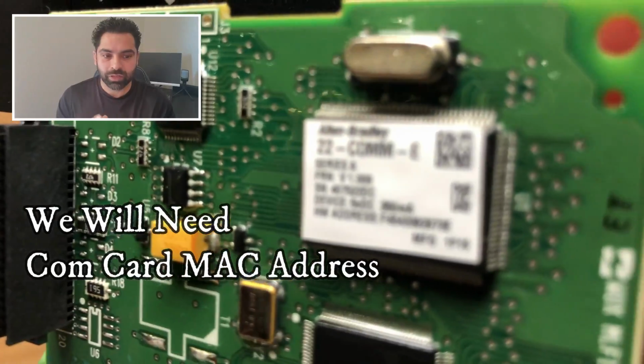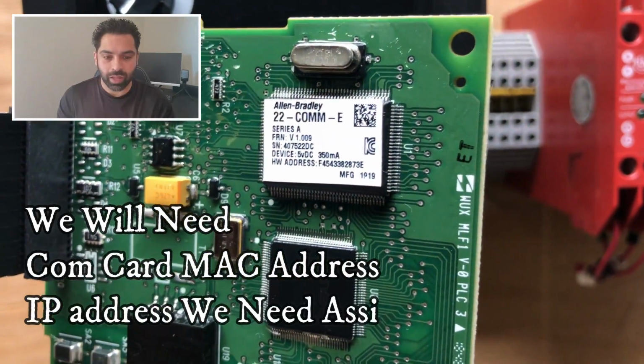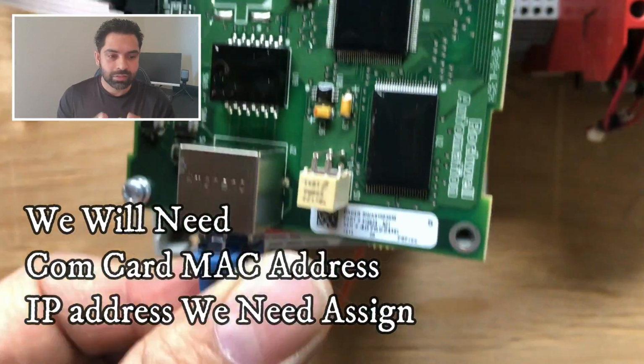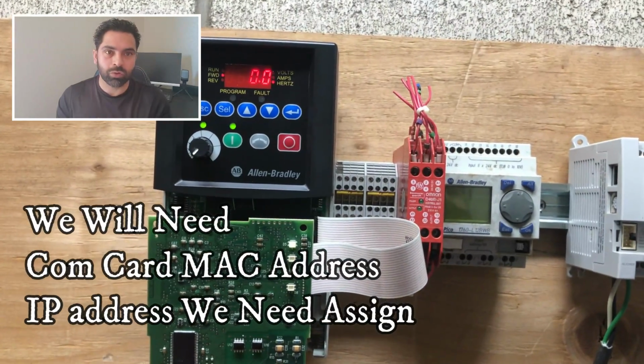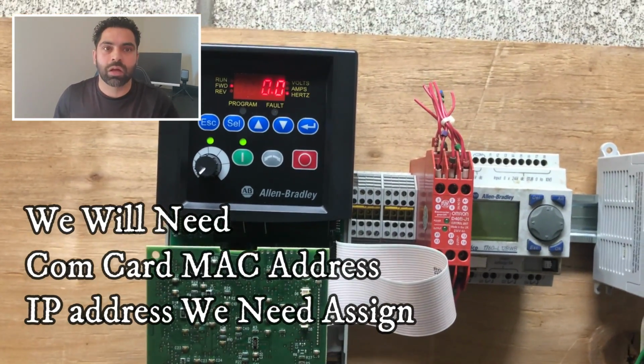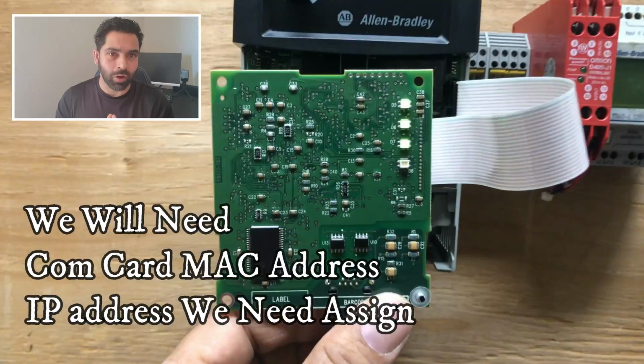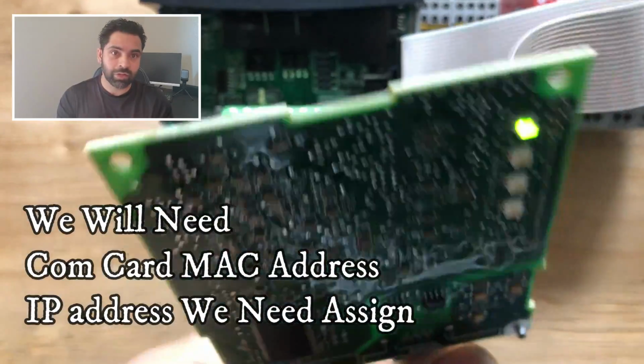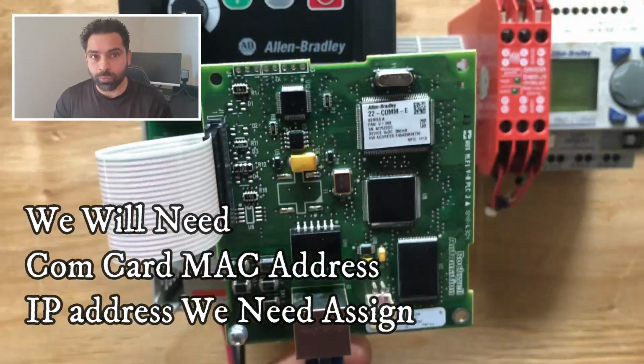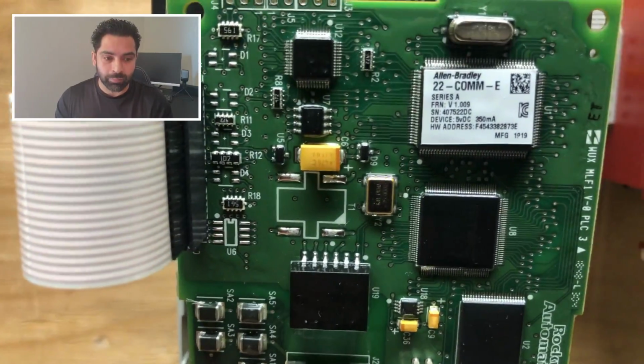Before you assign an IP address, there are a couple of things to remember. First, you need the MAC ID, or MAC address, from the COM card. Every COM card has a unique MAC address. Secondly, you need the IP address you are going to assign to this COM card. Once you have all the information gathered, we are going to use software called BootP to assign the IP address.